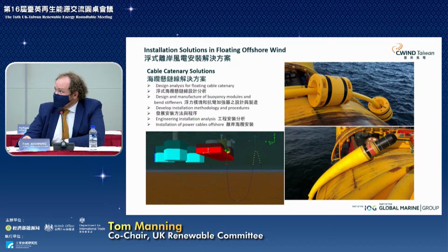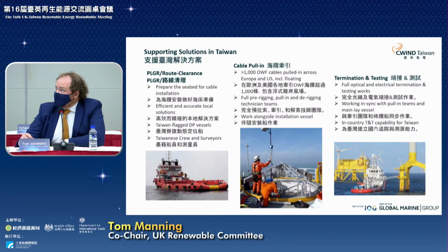A lot of focus for us as a cable installation company goes into the initial design analysis for the floating cable catenary. We look at how we can engineer and manufacture buoyancy modules and sections to stiffen the cable at the relative points, to make sure that cable is protected, particularly from excessive wear where it connects to the seabed and to the structure. We develop unique installation methodology and procedures to make sure those flotation sections are employed at the right place, and that we don't put undue stress or tension on the dynamic cable as it's pulled into the floating structure.